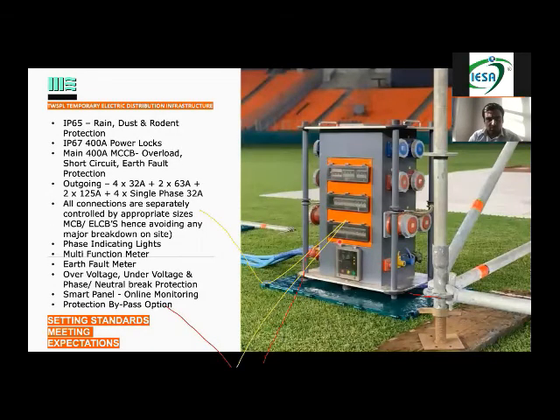Now this is the panel we are using for distributing the power, which is the most important for any exhibition or event, whether we are doing a live event, a wedding, whatever. Again, we have spoken about sockets, MCBs and power locks. So this is what we have designed. This is an IP65 panel, so that if it rains, we don't have to go and cover the panel. It is not like an open panel. Each and every socket is controlled by a separate MCB. There is an MCCB on top. The main power is coming from the power lock. The MCCB on top is thermal, so if there is any earth fault, it will automatically trip over there.